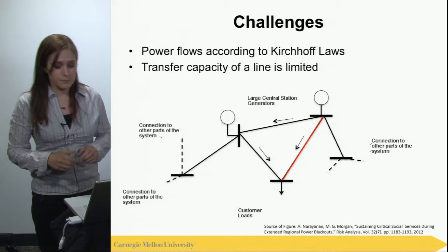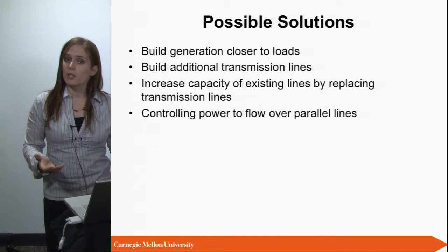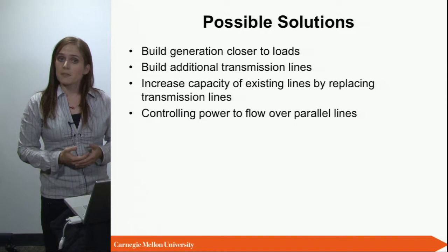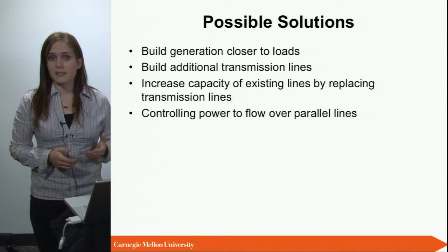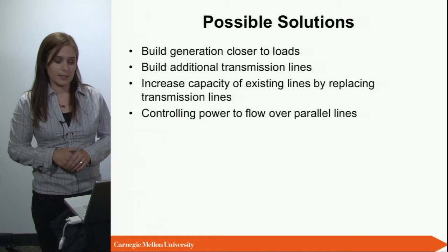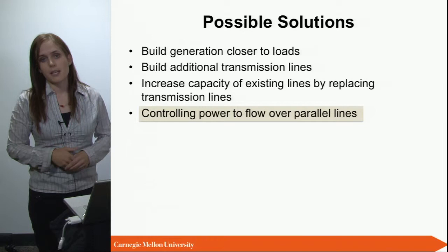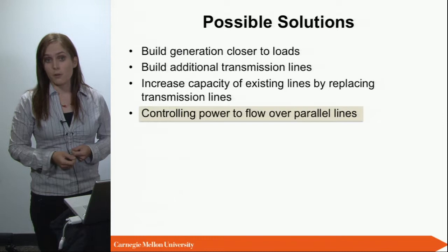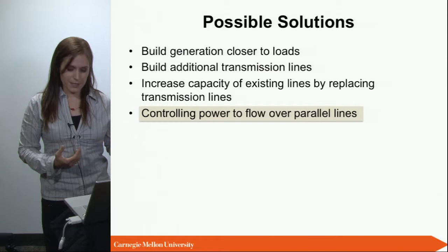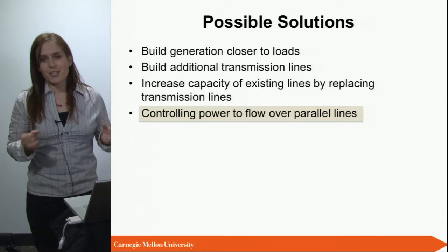Ways to solve this problem include building generation closer to load so less transmission is needed, building additional transmission lines for extra transfer capacity, or increasing the capacity of existing lines or transmission corridors by replacing or adding lines. Another option — which my group works on extensively — is controlling how power flows over the meshed network. Since Kirchhoff's laws are based on line parameters, if we can influence those parameters we can influence where power flows and essentially work around Kirchhoff's laws.